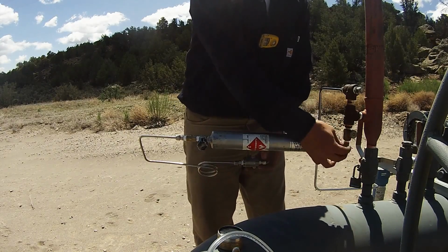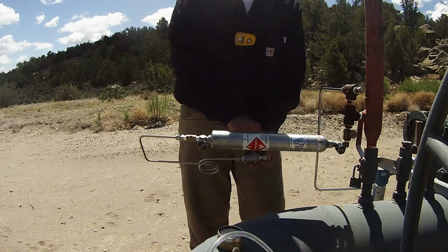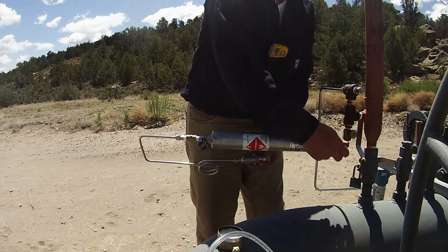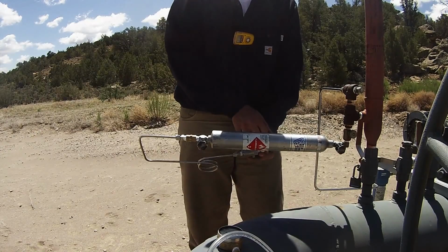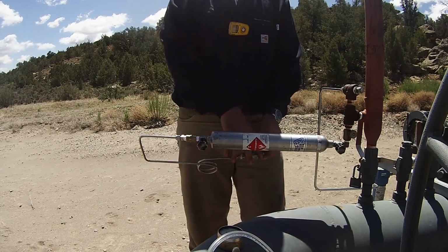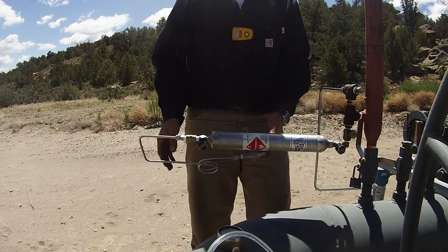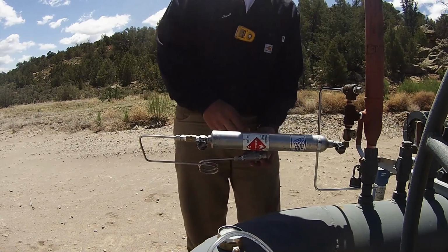The purge cycle is dictated by the pressure, and with this, I do believe it is 4 purge cycles for this pressure. There's purge cycle number 2. Purge cycle number 3. On the end of this valve, we do have a restriction to slow the gas down and not let any air back into the system. If any air were to get back in, this coil right here traps the air, not letting it back into the bottle.